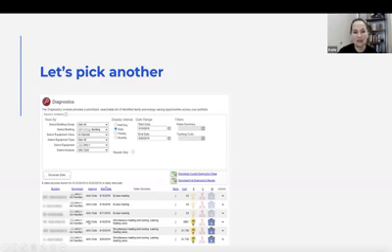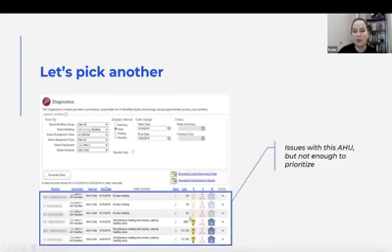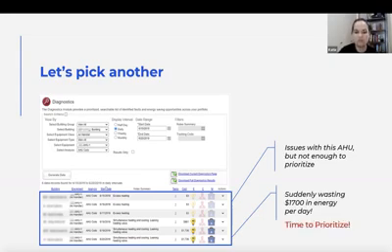We know this air handler has an issue, and we're looking back at daily issues that have happened over the past 6 days. And so when we first are looking at this, it's a $3 per day cost, which is not nothing, but also probably not our highest priority across campus. But then it starts to waste $1,700 a day, which it's time to prioritize when you see that.